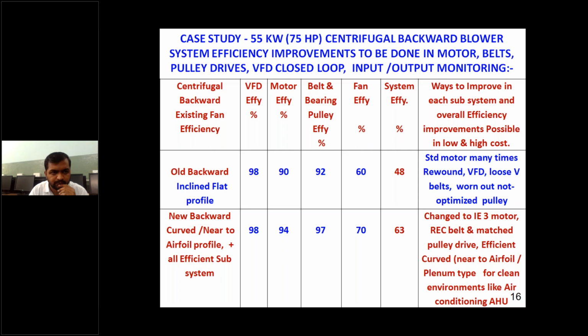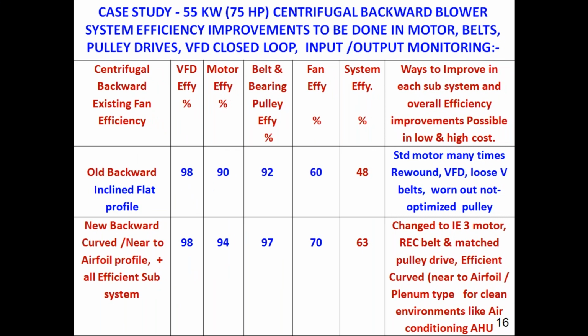If the same blower is replaced with a new backward curved inclined blower, that is near to an airfoil type blower, along with an excellent VFD and a better IE3 motor, a better resizing of belts and pulleys, and replacing the fan impeller from 60 to 70, overall it increases from almost 50 to 63%. So a 15 to 20% increase can be seen. Not only in the case of blowers, it can be applied to any of the systems. It can be in the case of pumps also. Replacing a monoblock pump with a multi-stage monoblock pump increases the efficiency by 20 to 25%.